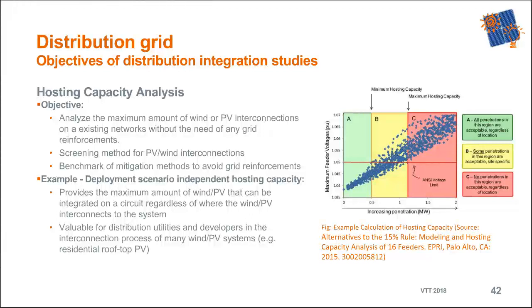In the report, I want to highlight deployment scenario independent hosting capacity analysis, which is helpful if you have, for example, rooftop PV or small residential systems where you don't know where future systems will be interconnected. You can run Monte Carlo simulations with thousands, maybe 10,000, different deployment scenarios in your distribution grid, and the output can be a scatter plot like shown here.